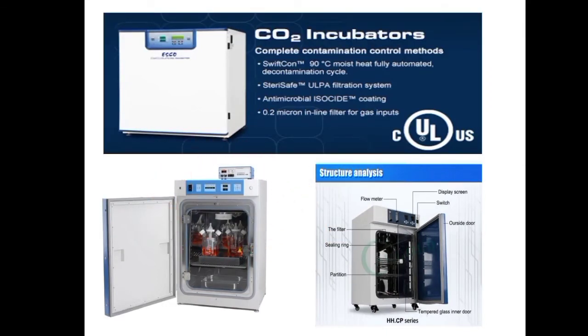Most of the CO2 incubators have a glass door as well as the regular doors, which provide additional protection against contamination. The interior is made of rust resistant materials such as stainless steel and should have as few sharp edges and grooves as possible to avoid any place where contamination could hide. In the sensitive field of cell cultivation, just one single germ can ruin weeks of work.